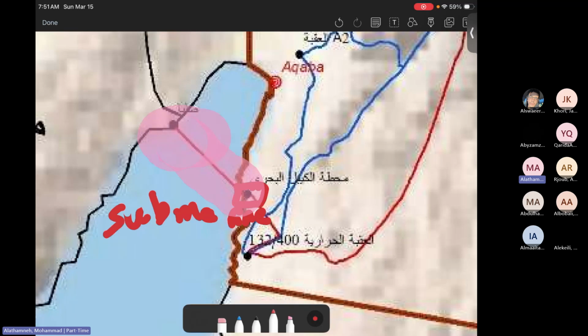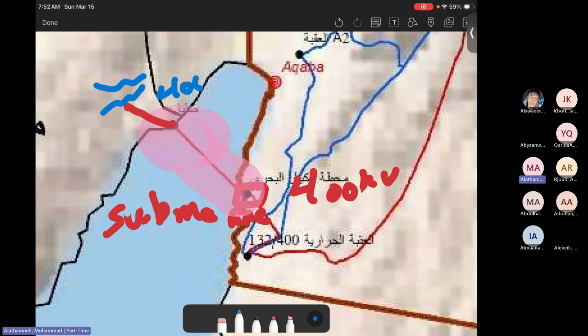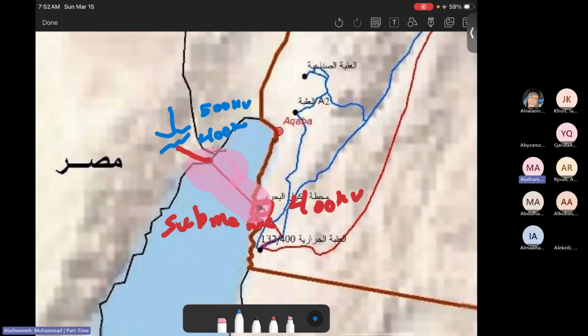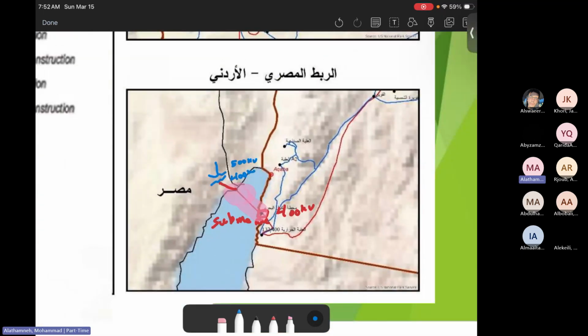This interconnection has 400 kilovolts in Jordan. In Taba, there is a substation with a step-up transformer converting 400 kilovolts to 500 kilovolts, going towards Sinai and Egypt. So the interconnection between Jordan and Egypt is still in service, and it's very beneficial for us.